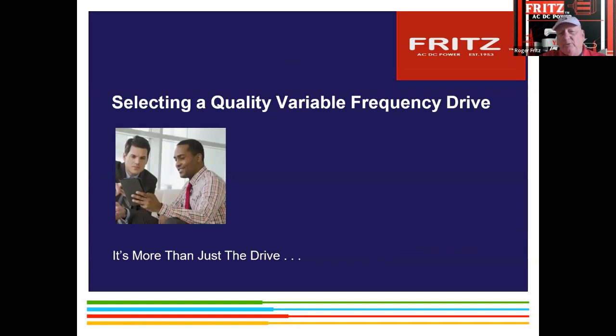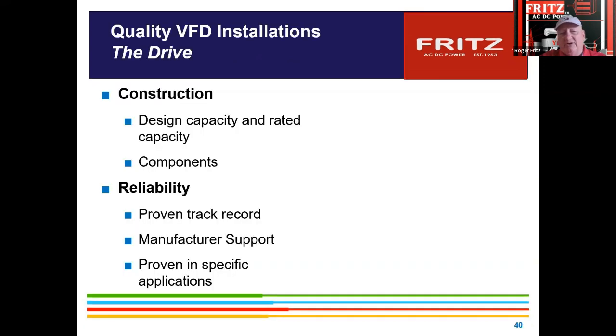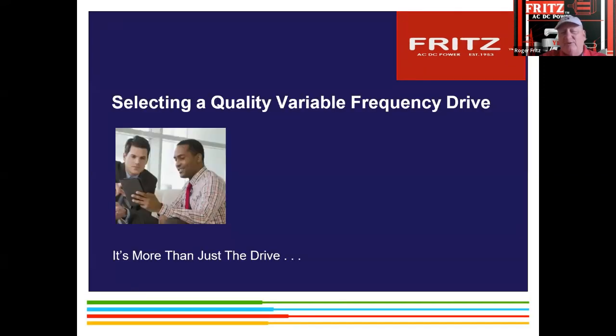We do highly recommend that you look at the quality of the drive controls. There are differences in drives, and one thing you can look at is the carrier frequency at which the motors can operate. Some really say you should never go over 4 or 5 kilohertz per wave. Well, the better ones go up to 10, 12. And that also means the transistor can fire faster and build a better waveform.